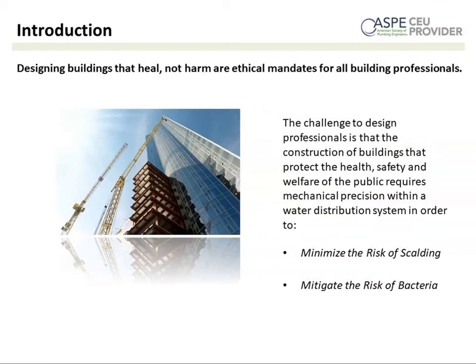So again, the challenge for professionals is minimizing scalding risk and at the same time minimizing the risk of Legionella and bacteria. And that's tricky because when you raise hot water temperature, you're killing bacteria, but you're increasing the risk of scalding, and vice versa. When you lower water temperature, your risk of scalding goes down, but the risk of bacteria goes up. So this is a real challenge, and that's why you have to have a complete systems approach to hot water.